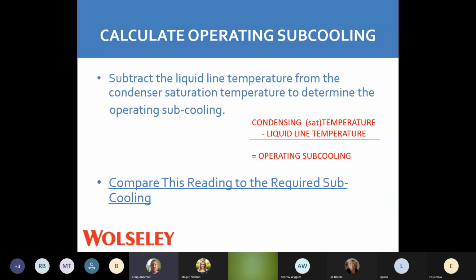Condensing saturation temperature minus your liquid line temperature is going to give us our operating subcool. So we're checking both. We want to make sure both are in the right parameters, whether it's our subcooling or our superheat. We need to make sure we know if we have a piston inside or a TX valve inside. Same thing outside. It can determine what kind of readings we're looking for when we're doing these calculations.